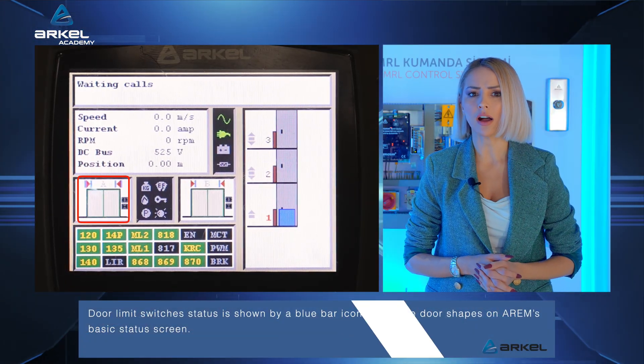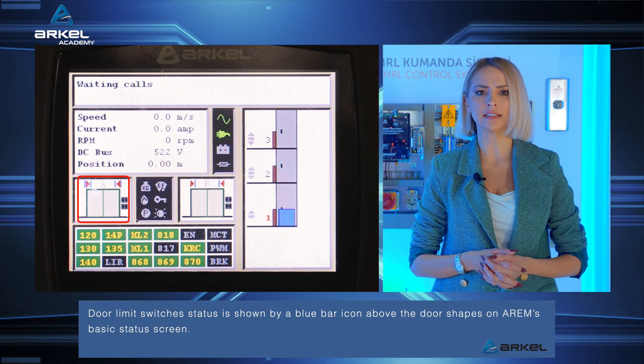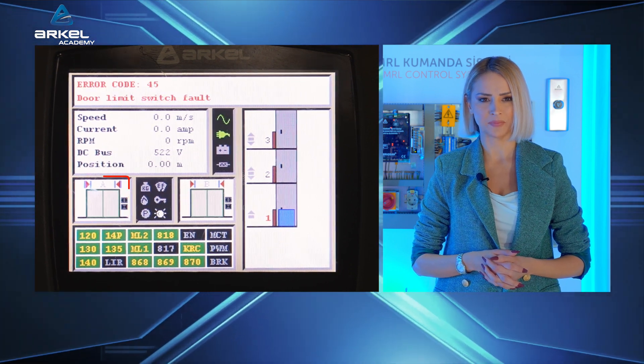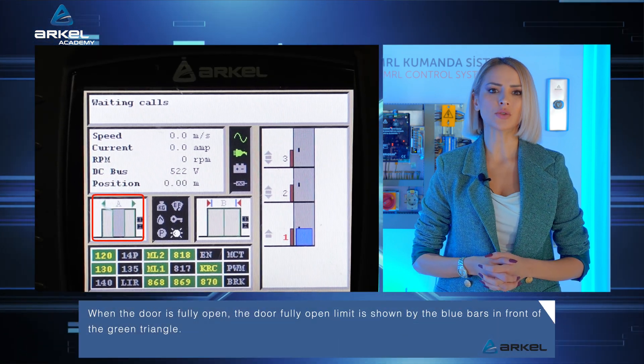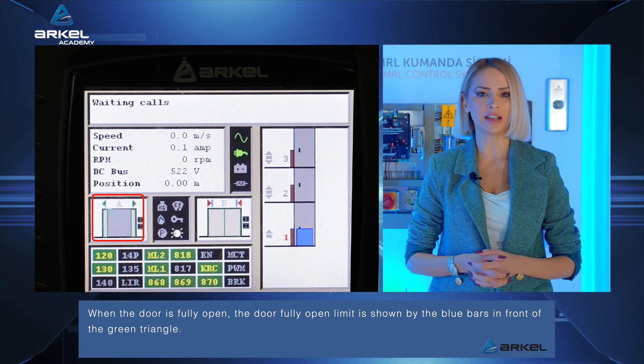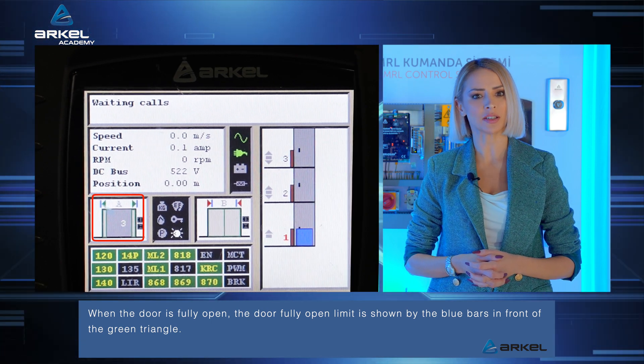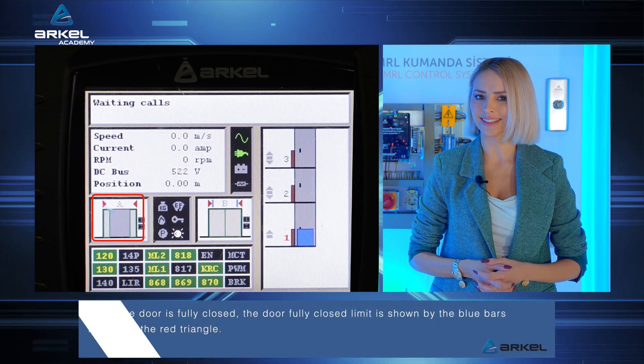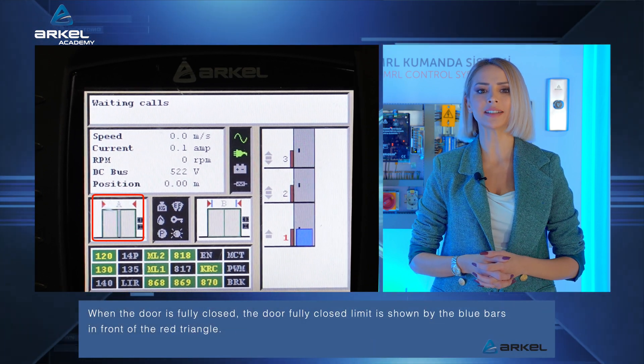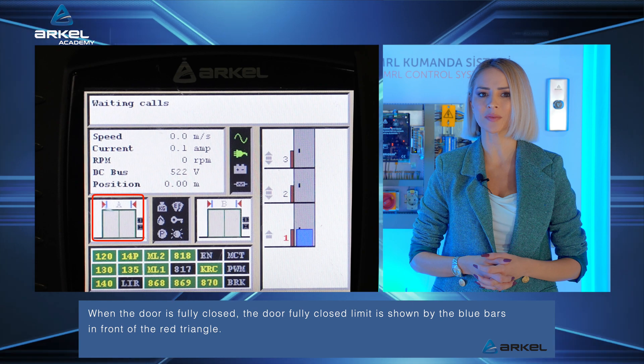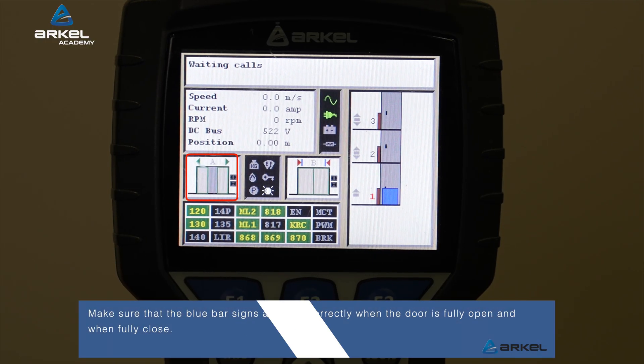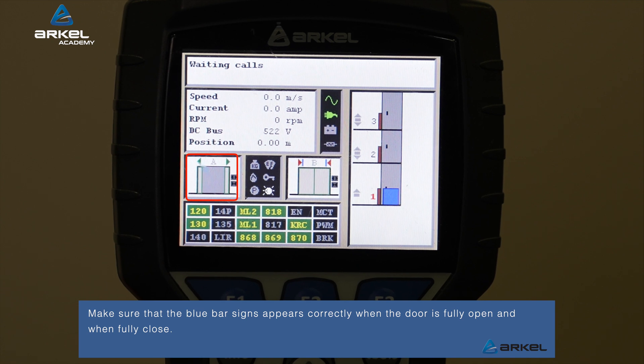Door limit switch status is shown by a blue bar icon above the door shapes on AREM's basic status screen. When the door is fully open, the door fully open limit is shown by the blue bars in front of the green triangle. When the door is fully closed, the door fully closed limit is shown by the blue bars in front of the red triangle. Make sure that the blue bar signs appear correctly when the door is fully open and when the door is fully closed.